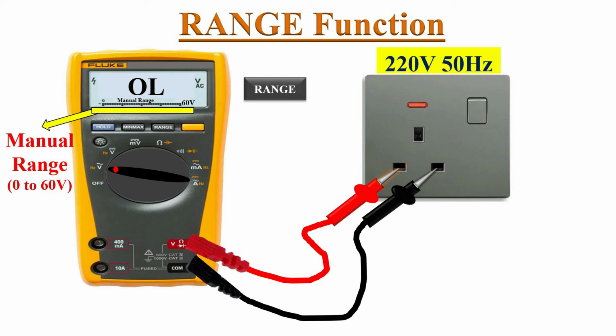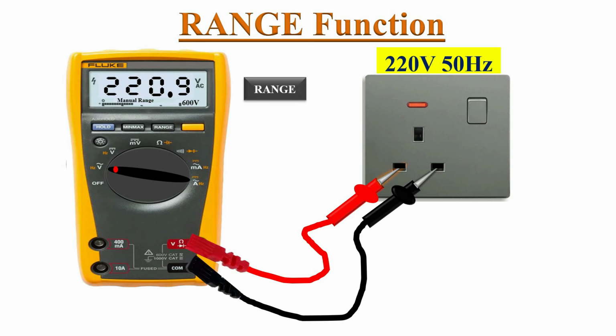But this range is also smaller for the 220 volt AC measurement. So the meter still displays OL. Push the range button again. Now the meter will enter into the 0 to 600 volts range. So the multimeter will display the measurement value as 220.9 volts AC.